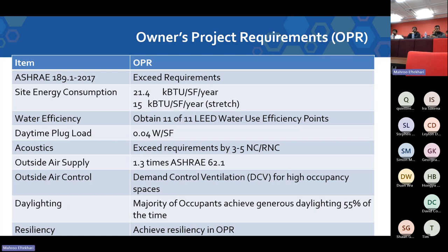We wanted to exceed noise requirements by 3 to 5 NC for a standard office environment. For outside air supply, we wanted 1.3 times the ASHRAE 62.1 requirement, about 30% more ventilation - as it turns out in COVID, that was not a bad thing. We also wanted outside air demand control for high occupancy spaces, and daylighting for the majority of occupants 55% of the time. Then we needed to make sure we handled resiliency.